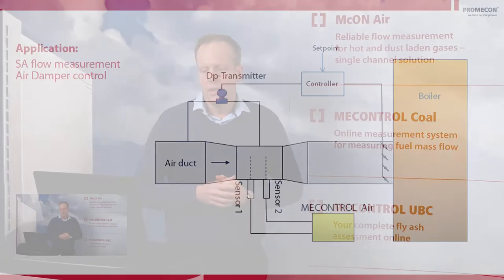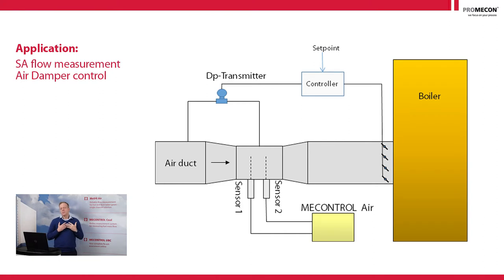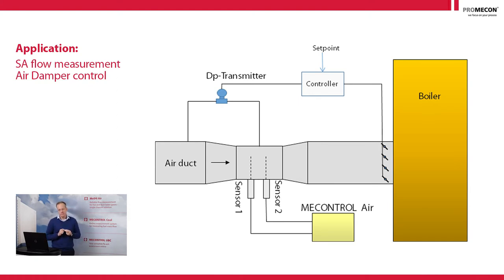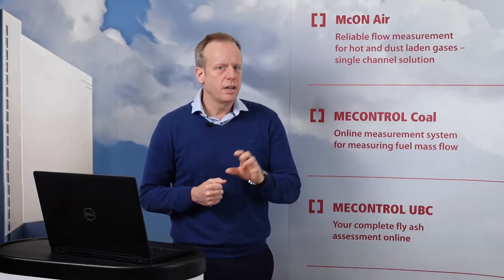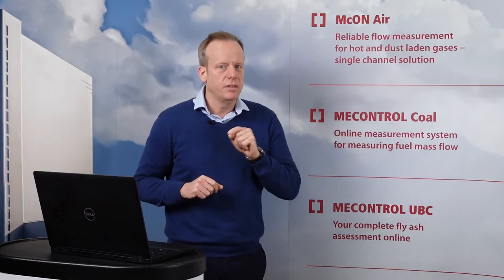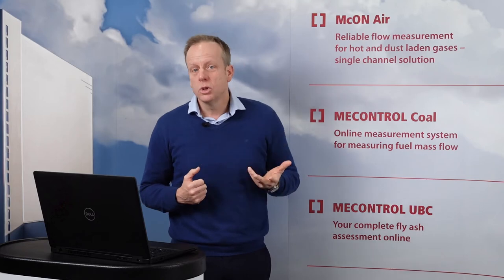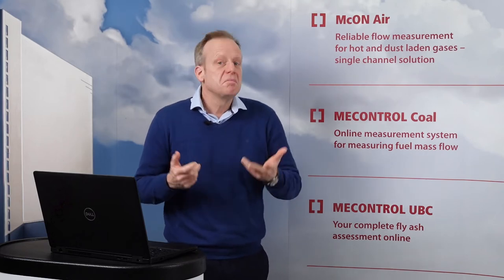Let's have a look. This slide shows you how an air flow measurement normally works. You have a venturi, an aerofoil, or some form of tapered section in a duct, and you measure the static and dynamic pressure across this section. According to the Bernoulli equation, you calculate the mass flow that goes over this venturi or aerofoil. Now, how much differential pressure are you measuring at this location? About 20 millibars — 16 millibars? Not much.